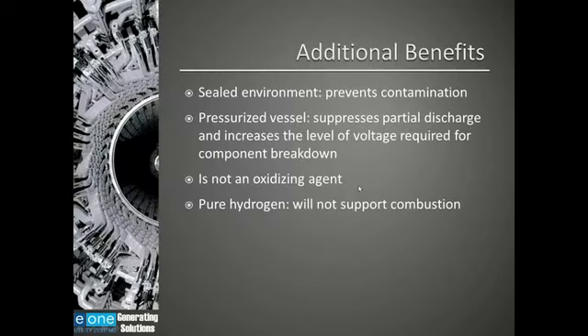There are additional benefits of using hydrogen as a cooling gas. Because the generator is sealed, you're less likely to get contaminants in the generator as you would an air-cooled generator. Because it's a pressurized vessel, it suppresses partial discharge and also increases the level of voltage that is required for a component to break down. Hydrogen is not an oxidizing agent as air is, and pure hydrogen will not support combustion. Also, because bottled hydrogen is typically very dry, the moisture or dew point in the generator will be very low.